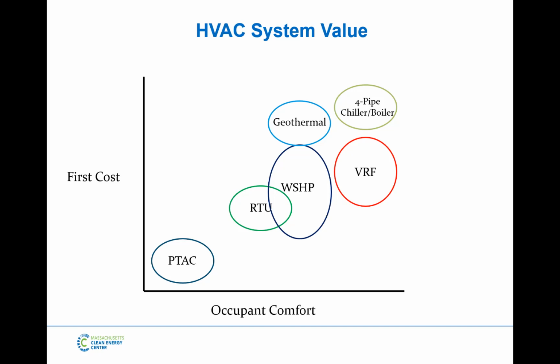Stuff like a PTAC, yeah, you have the benefit of pulling in outside air, but then you have the problem of, yes, you're bringing in fresh air, but now it's untreated, it's not using energy recovery, you're gonna have more temperature swings. So this is just trying to sum up stuff on a single slide. So I'm using occupant comfort as a general, if we're looking at zoning, you could just say occupant happiness. I mean, there's a lot of different things that go into it, but in general, stuff like ventilation is gonna be how you handle it. It's a similar thought process for all technologies on this board here.